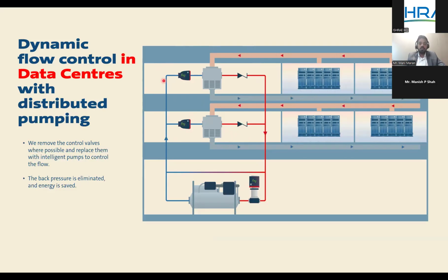So as I said, by removing the valve, what we are doing is pretty simple. We are just removing the pressure which is created by the valve, and that's straight away savings. And we have a dedicated unit, a decentralized pump, a coil pump connected to each unit. And now the commissioning is very easy because we are moving out of manual balancing. These are self-balancing systems. We can just connect the pumps and start the pumps, and the system will balance by itself between the primary and secondary, which we will see in a moment.